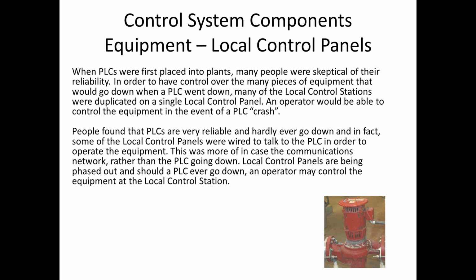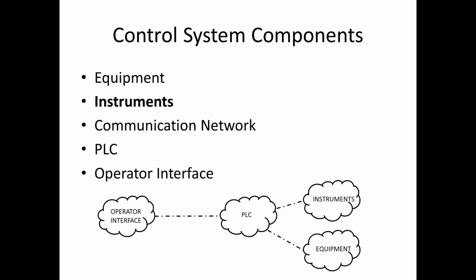As time went on, the PLCs have proven themselves to be pretty reliable, and the cost and expense of having local control panels was getting more and more difficult to justify. Some plants still put them in, but more and more plants are finding that they really don't need those local control panels. In the unlikely event that a PLC does go down, the operators can go from station to station and manually control a piece of equipment right at the location where the equipment is. So that talks about the equipment.